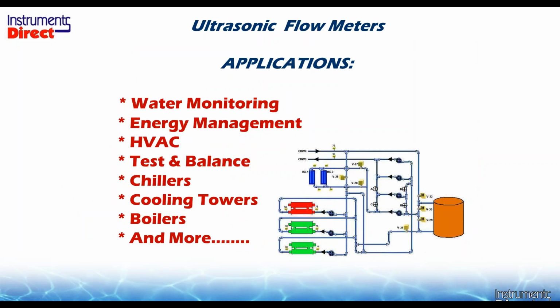And as I said, transit time technology works on all applications that have a full pipe condition, pressurized not required. Line size is 1/2 inch and up. They work on ultra pure liquids, so you can work on your DI water, demineralized water. You can work on jet fuel, gasoline, various chemicals. You can work on water, well water, chill water, hot water. You can work on sewage, and you can work up to about 2% suspended solids. So it doesn't work on oatmeal, and it doesn't work on sludge. That's where you put your ultrasonic Doppler flow meter. So give us a full pipe, and away you go.